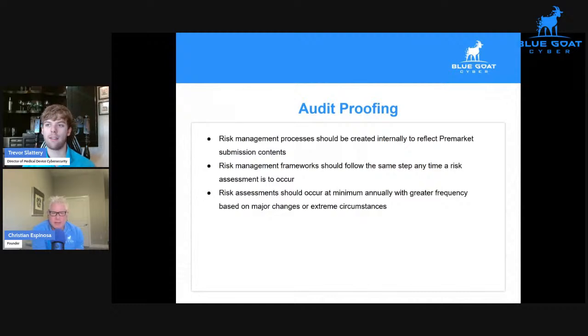Probably one of the more common things that we see in deficiency notices from the FDA is that your risk assessment methodology uses qualitative methods or language such as probability or likelihood. Probability can be very difficult to define. If we pick any one problem, I might say it has a 1 in 100 chance of occurring, and you might say it has 1 in 1,000 chance of occurring. And if we're not able to provide a clear justification on that number, then it's essentially just saying, leave it up to my assessment of it.